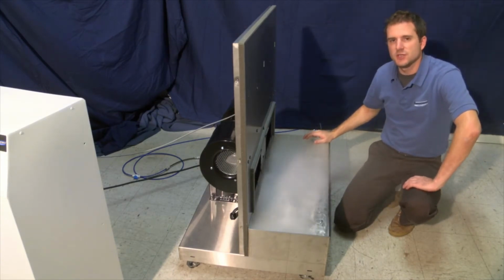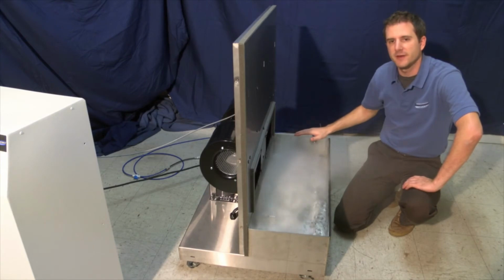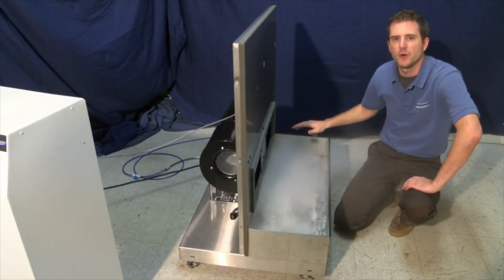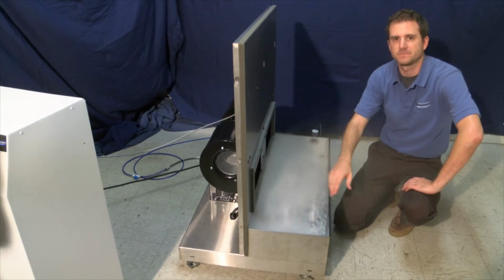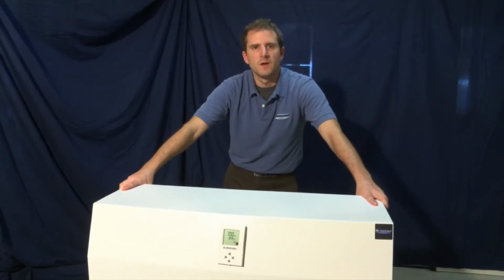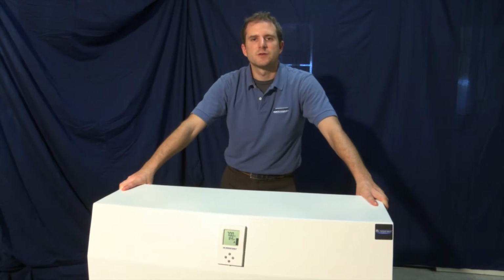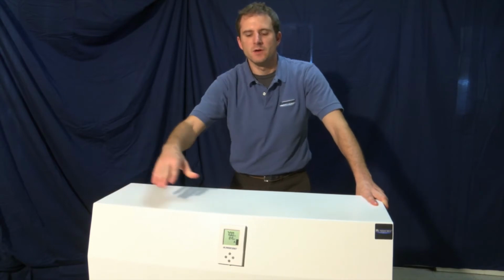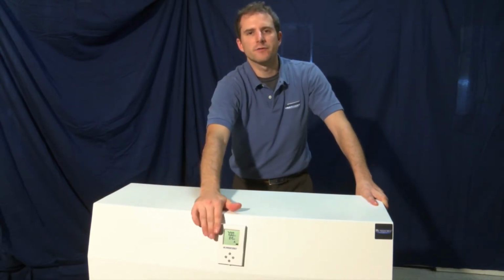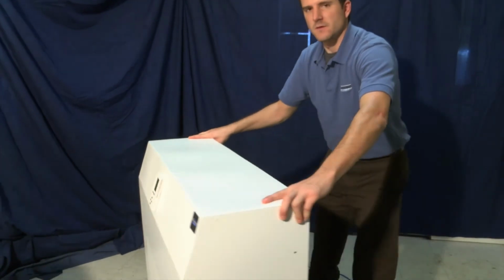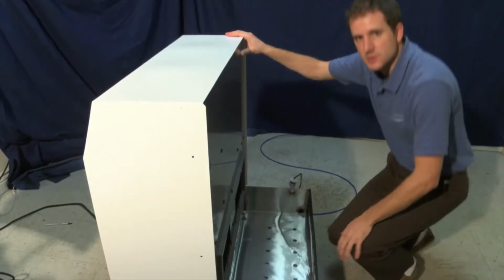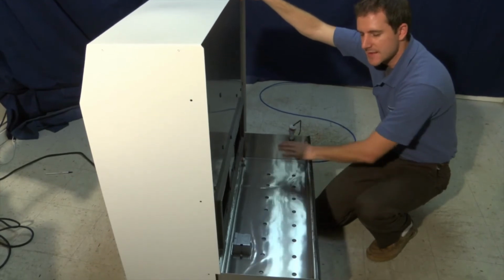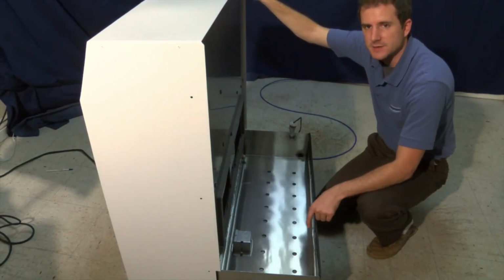Each transducer should have a 2 to 3 inch fountain or finger of water off of it, and the mist would roll off that fountain. All transducers should be operating at the same time in a uniform pattern. Another scenario that can keep the transducers from operating is low water or not enough water supplied to the humidifier. Note the humidistat is on and calling for humidity, but the transducers are not operating. This is because there's not enough water in the water pan for them to operate safely.